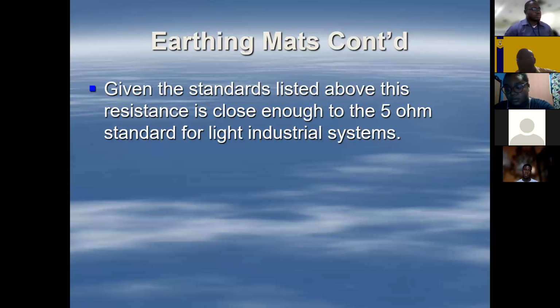As a matter of fact, I'm quite excited about this, because when I left CAS, this was one of the first projects I was thrown into. At that time I went into telecoms, and I was working in Mandeville. One of the issues we had was that every time the clouds got dark, we would be fretting, because one of the high areas in Manchester has a transmitter, and regardless of which radio station you listen to, they have a transmitter there. Once it got overcast, we started worrying about lightning strikes. The earthing project was something I was thrown into, and it's very rewarding to measure the earth resistance, improve it, and see the solution.